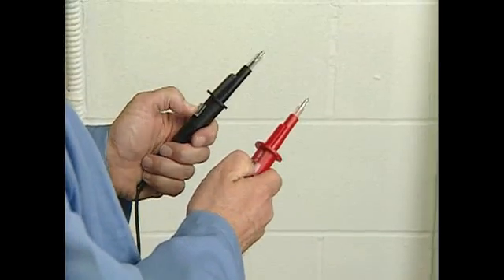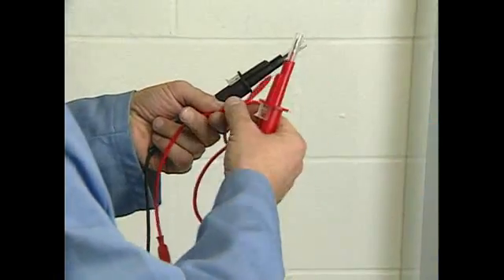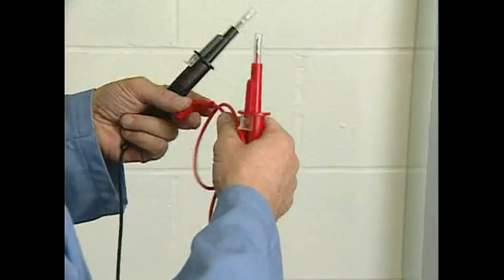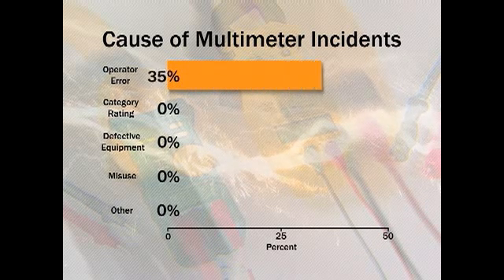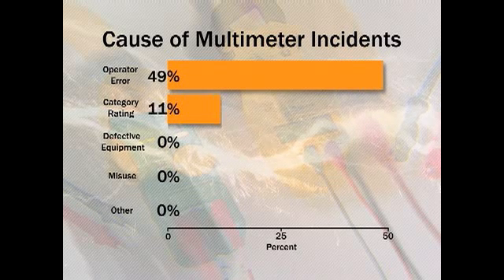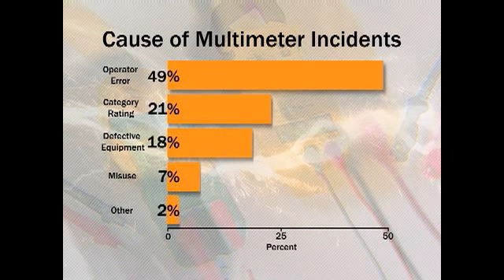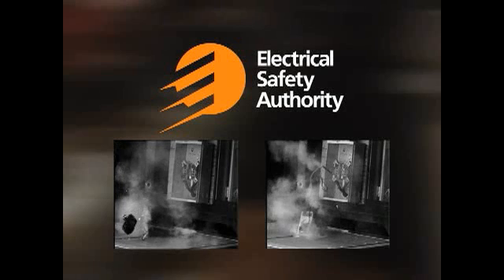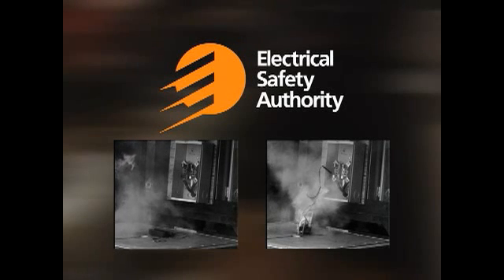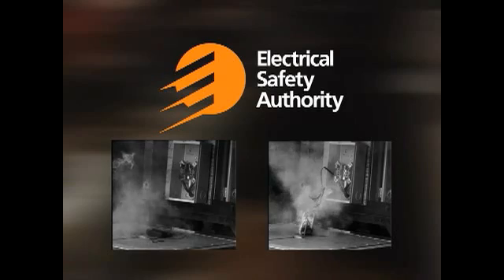Always check your meter and fused leads to ensure they're in good operating condition. ESA's survey respondents reported that injuries with multimeters occurred due to operator error at 49%, category rating at 21%, defective equipment at 18%, and misuse at 7%. Recent studies and simulations commissioned by the Electrical Safety Authority conclude that the use of fused leads is a highly effective way to prevent possible catastrophic results if a multimeter is being used inappropriately or experiences an internal failure.